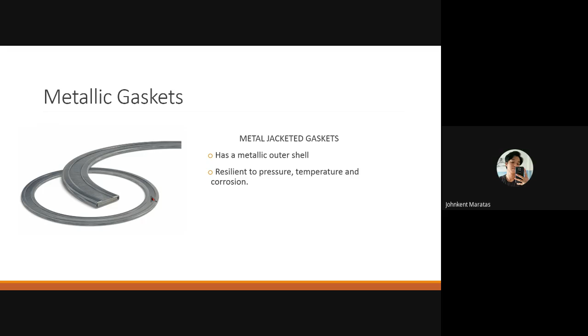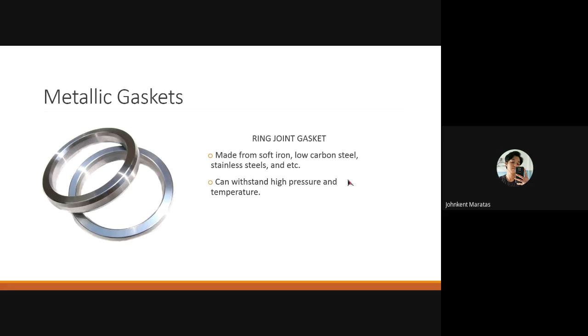Another example is the ring joint gasket. These are solid metal gaskets used to withstand high pressure and temperature, and they are employed where corrosive agents are present. It is recommended that the gasket material be softer than the mating flanges. Ring joint gaskets are generally made from soft iron, low carbon steel, alloy steels, and stainless steels, and can also be made from some non-ferrous metals, for example high nickel alloys, super alloy steels, titanium, and so on.